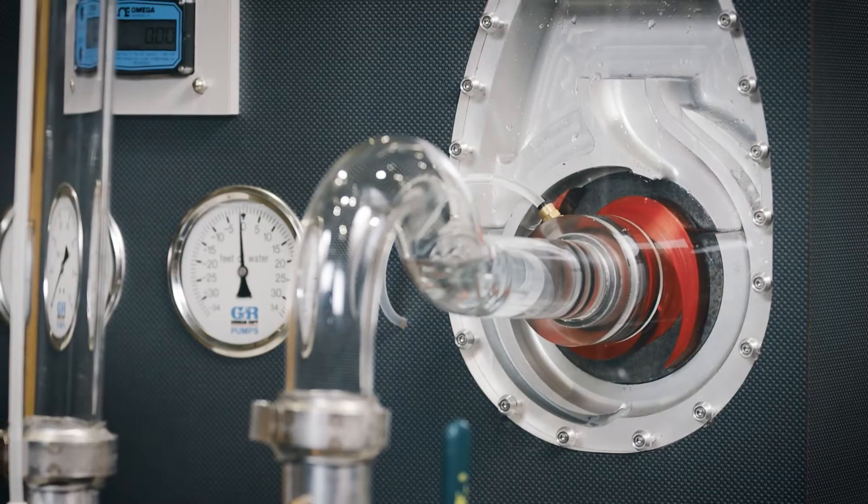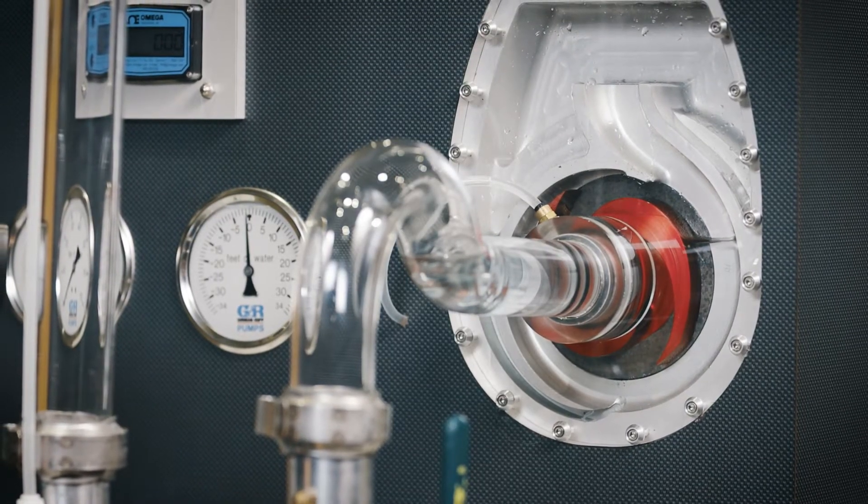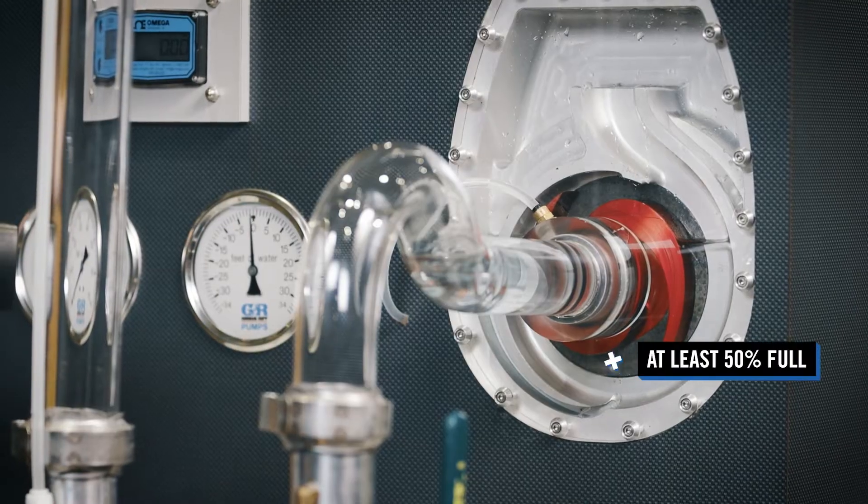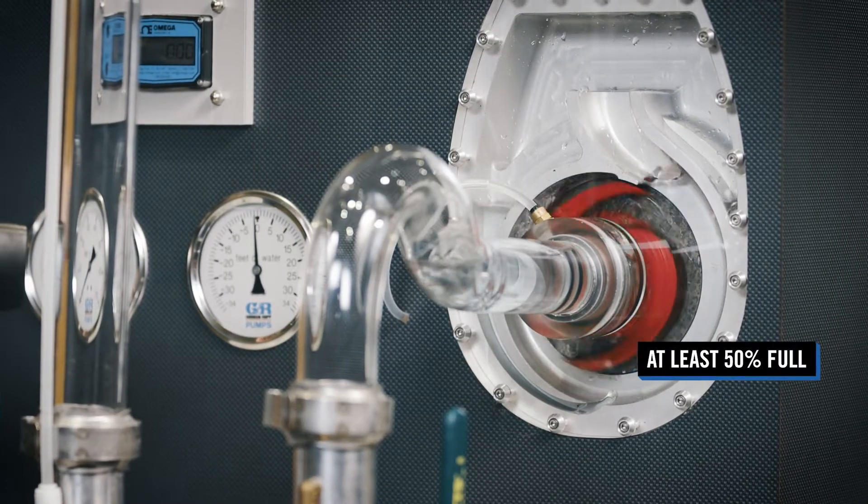Before initiating a reprime cycle, a self-priming centrifugal pump requires at least half of its casing to be filled with water.